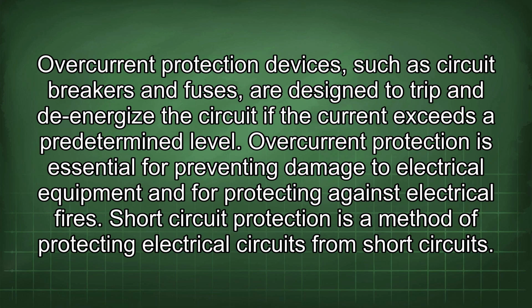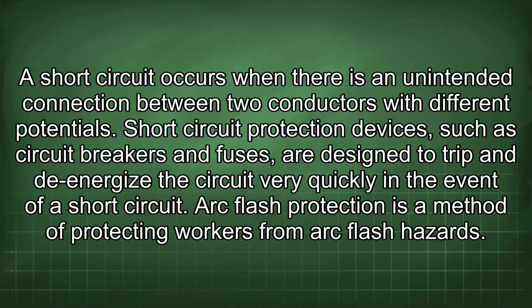Short circuit protection is a method of protecting electrical circuits from short circuits. A short circuit occurs when there is an unintended connection between two conductors with different potentials. Short circuit protection devices, such as circuit breakers and fuses, are designed to trip and de-energize the circuit very quickly in the event of a short circuit.